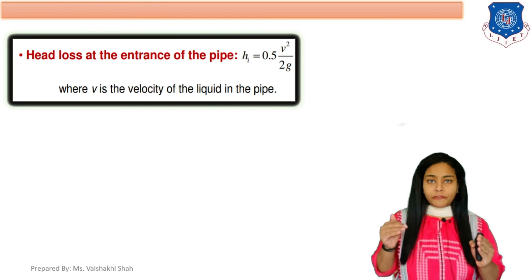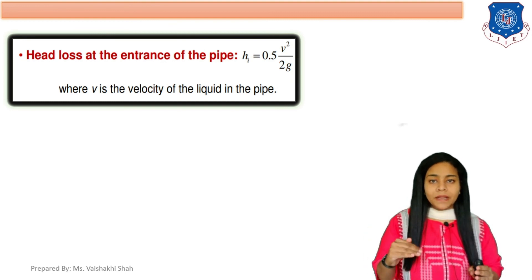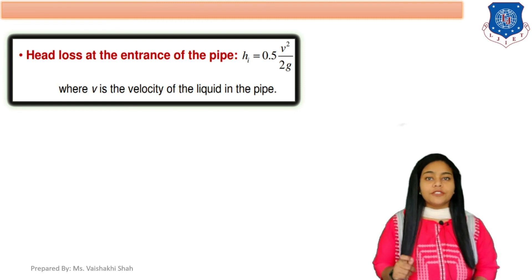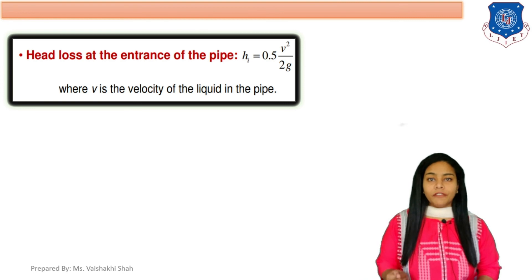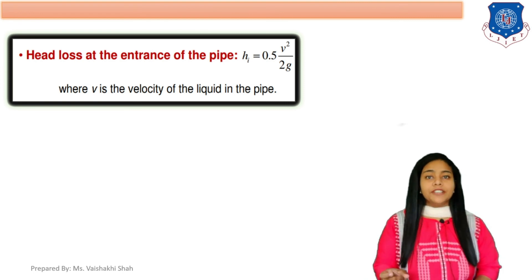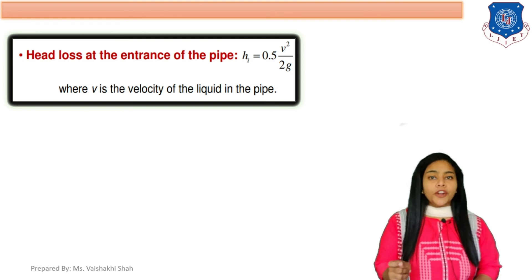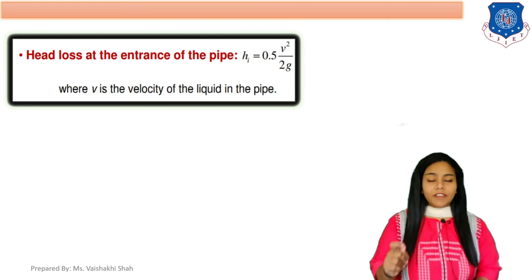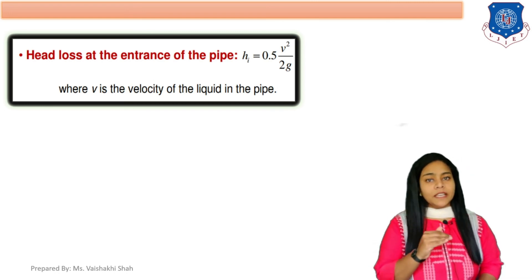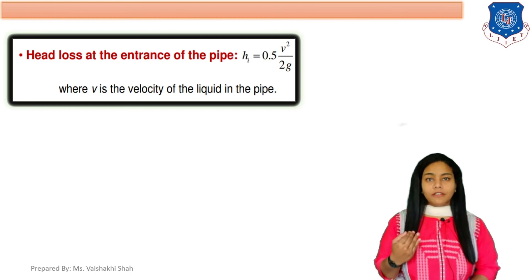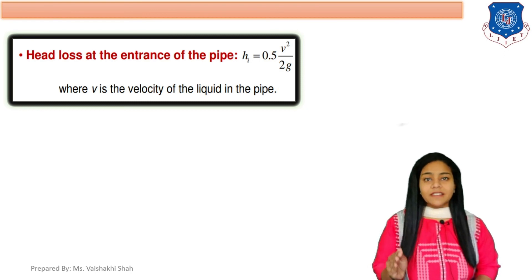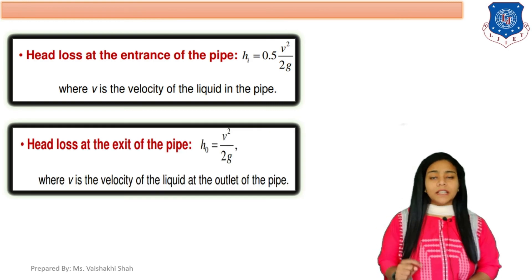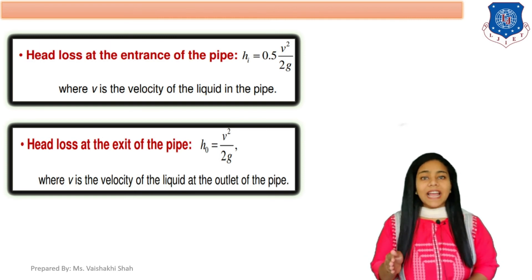When the fluid enters a pipe there is some amount of head loss, indicated as hi — head loss due to entrance of the pipe. The equation for head loss at entrance is 0.5 V² / 2g, where V is the velocity of liquid flowing in the pipe. Remember this equation: head loss at entrance = 0.5 V² / 2g.